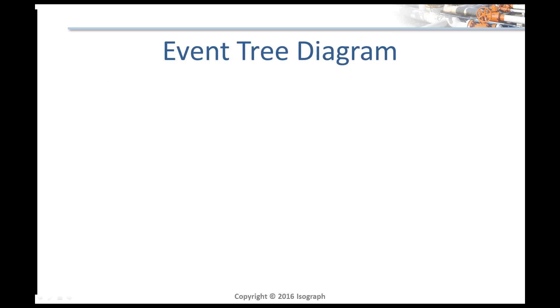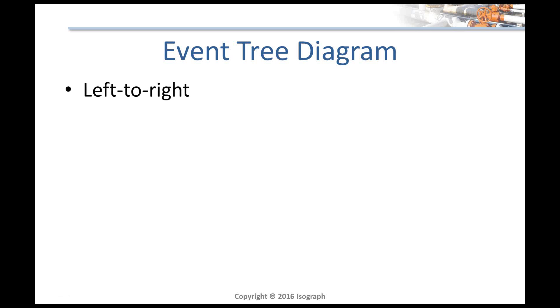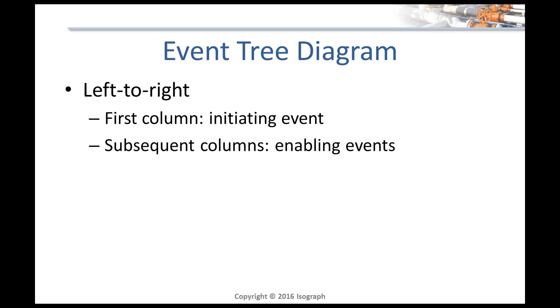Before we look at event tree examples, let me briefly explain what the event tree diagram looks like. You might be familiar with fault trees which are read top-down — you have your top event at the top and it goes down. Event trees are read left to right. Your initiating event is the leftmost column and you read left to right. The subsequent columns are enabling events — things that could influence the possible outcome. Based on the behavior of these systems, they lead you to one consequence or another.